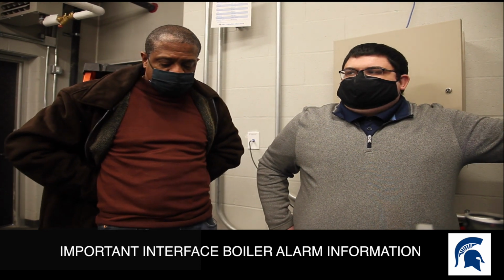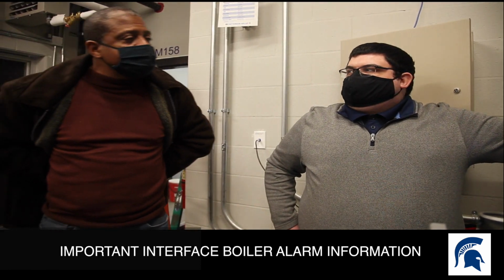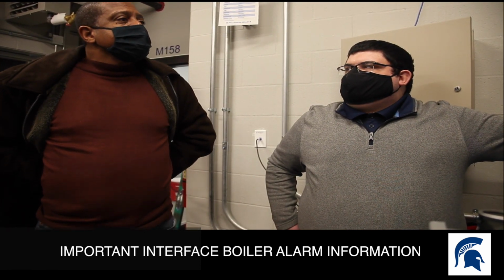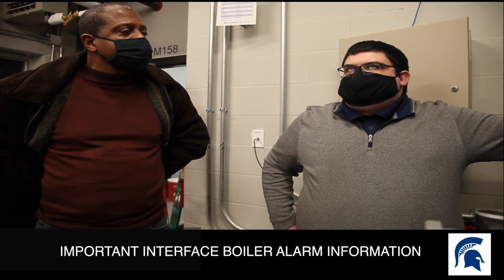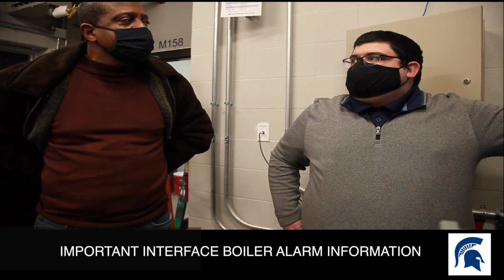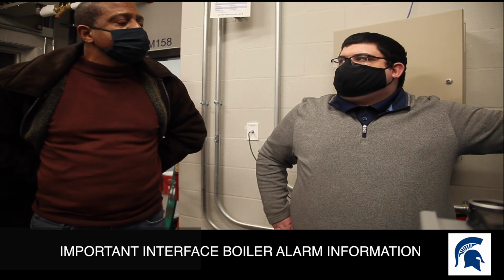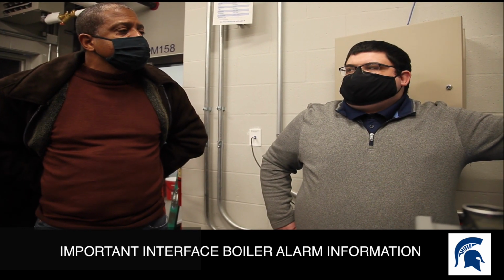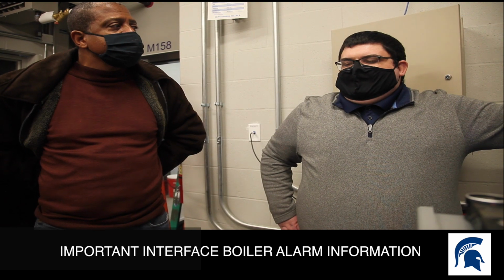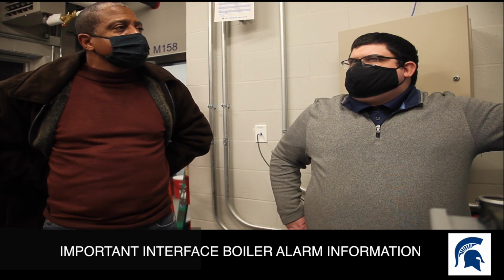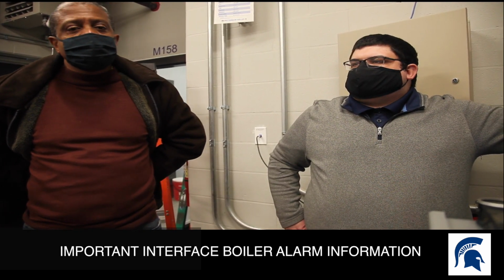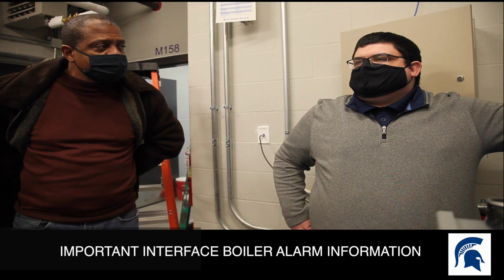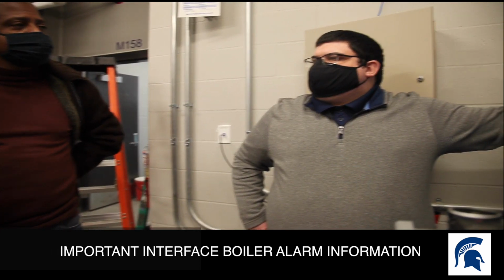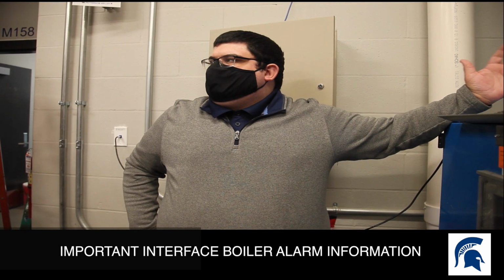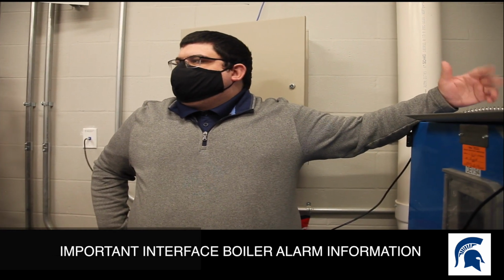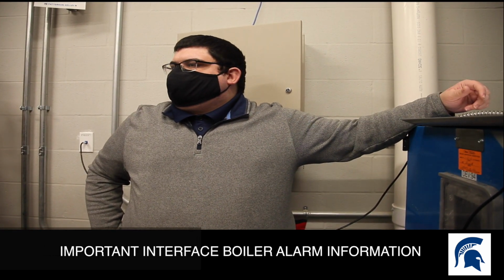Same things are configured for the rooftops. If any of those alarms go active, it sends an email. And then for the space temperatures as well, so your VAVs out in the building. We have those set up right now. If any of them get below 60 degrees, I think it's either 55 or 60, I'd have to double check, for like 15 minutes, it'll send an alarm and say, hey, VAV 1-10 is too low, you want to go check it.